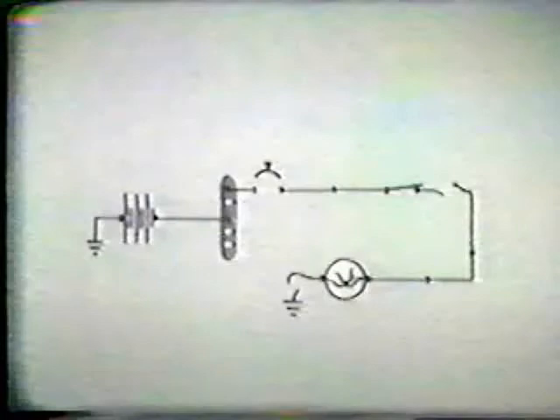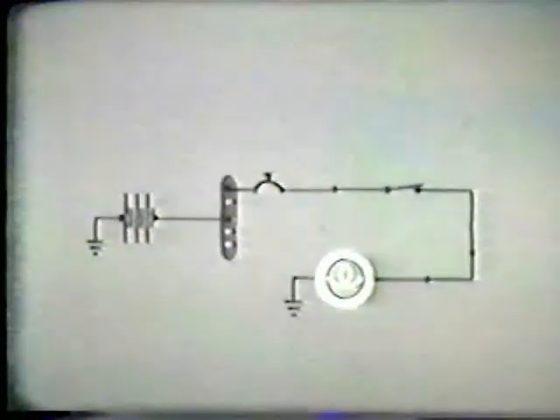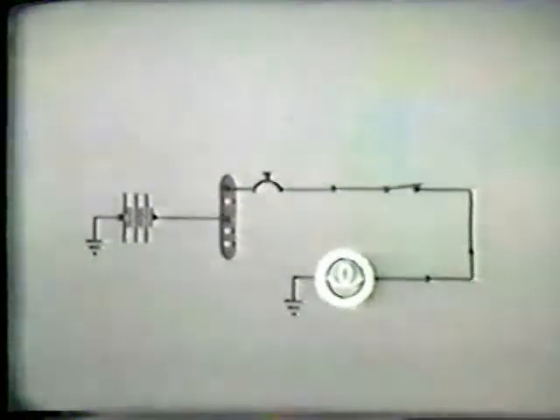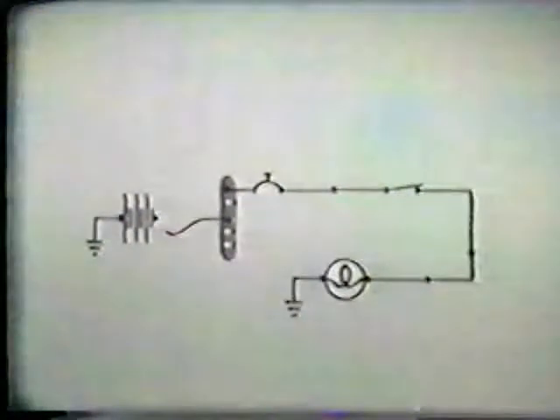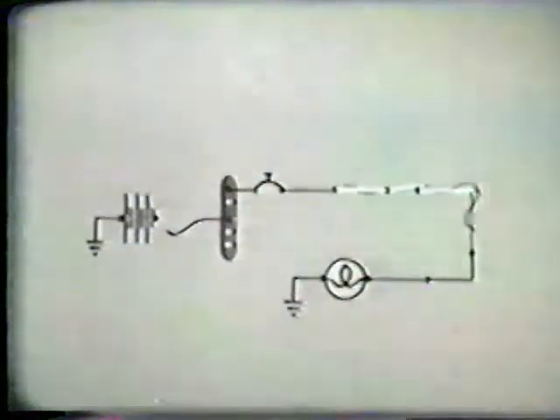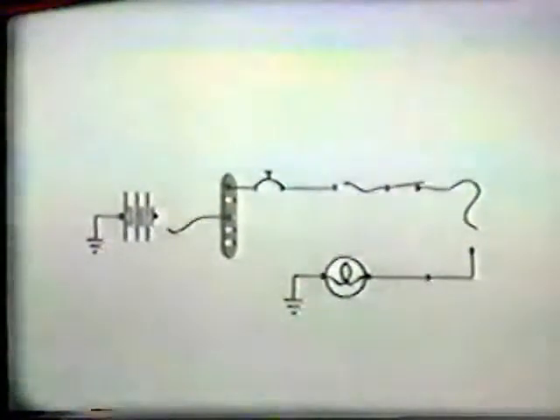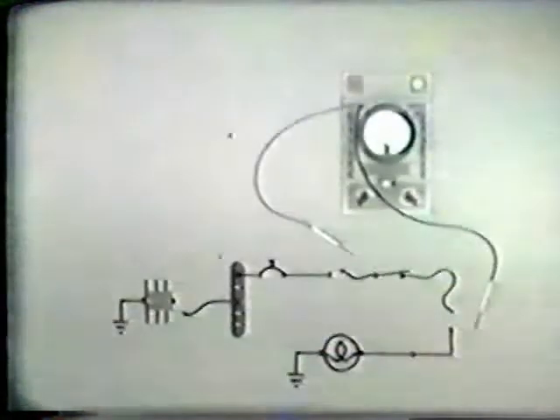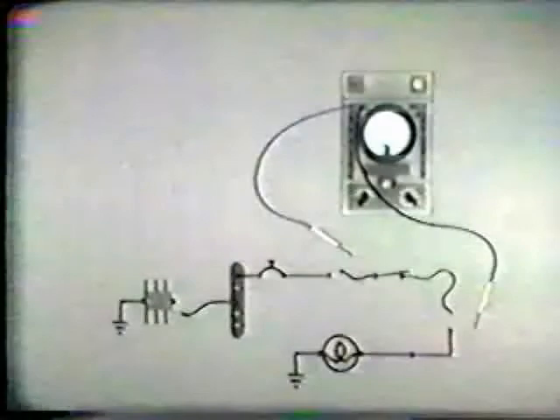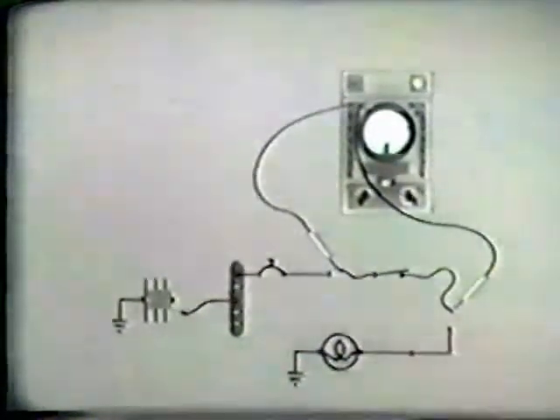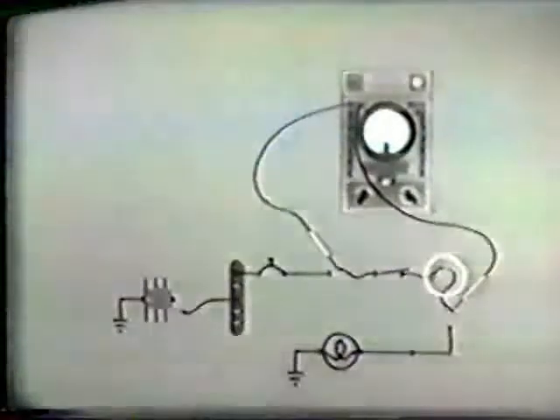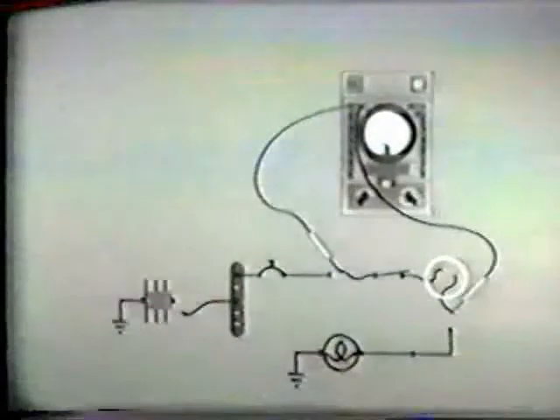To test for continuity in a given part of a circuit with an ohm meter, we must first disconnect the source of power. Then we isolate the part of the circuit which is being tested. Isolation prevents false ohm meter indications. Next, we connect the test leads to the two isolated ends of the part of the circuit under test. Since the scale shows a reading, we know the circuit is unbroken. It has continuity. If a wire is broken or there is some other break in the circuit, the needle will not move, indicating that the circuit does not have continuity.